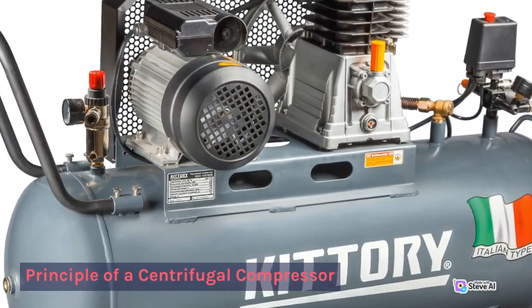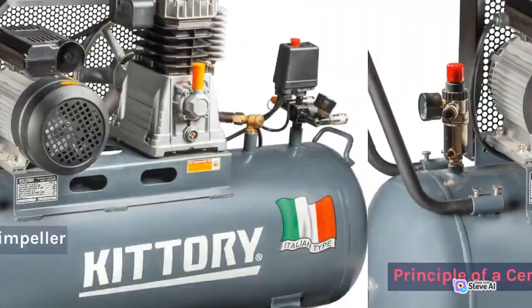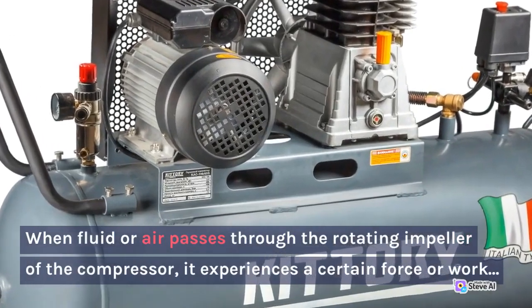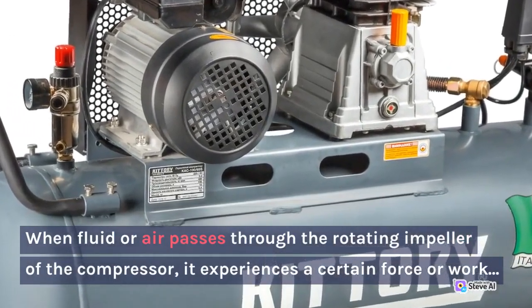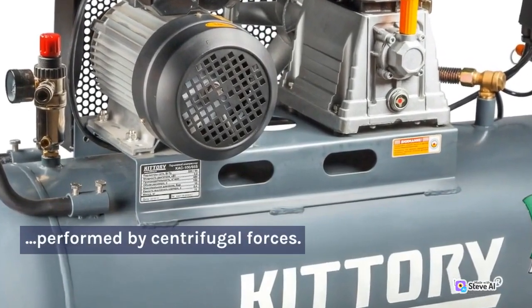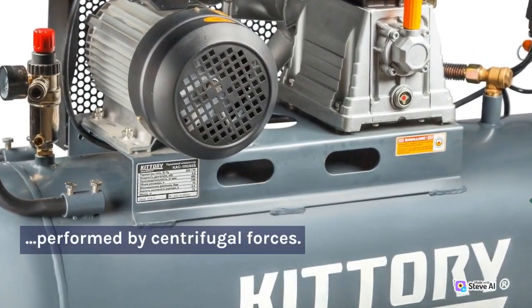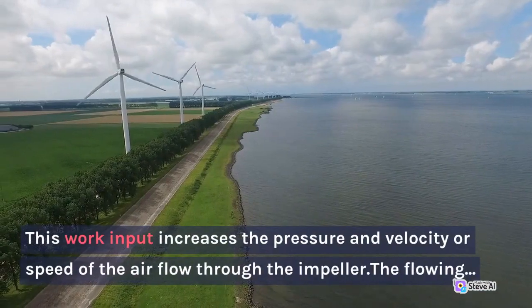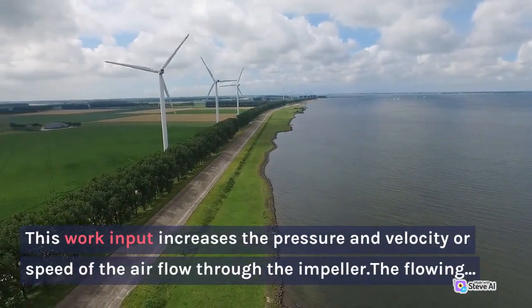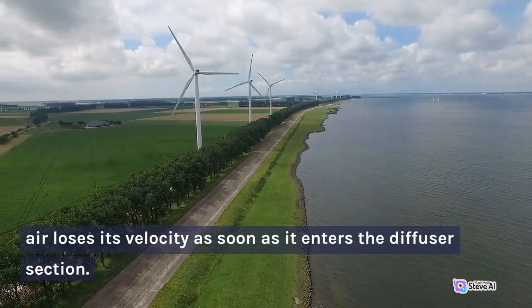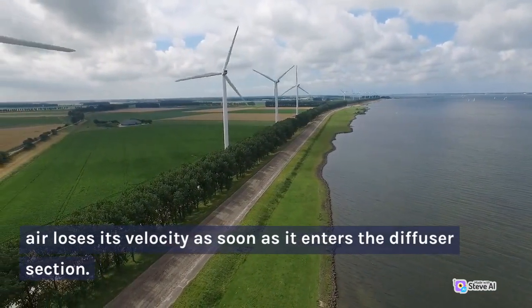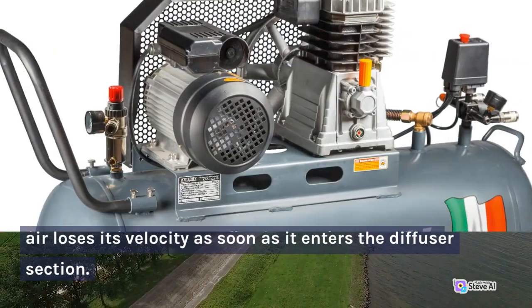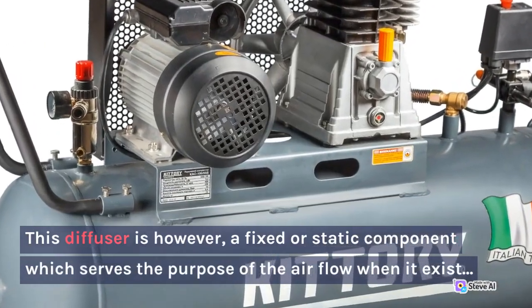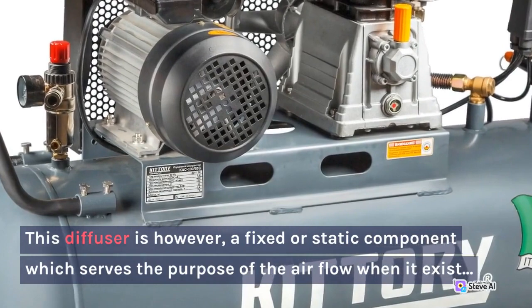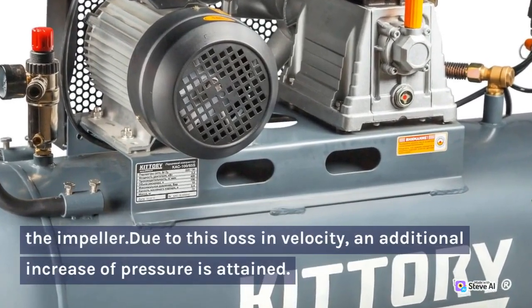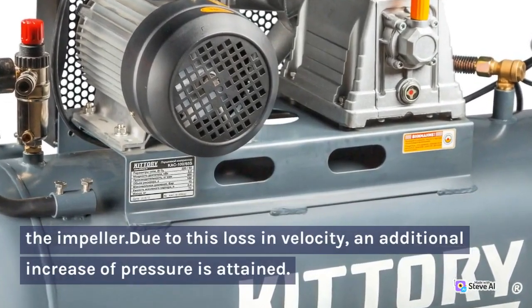Principle of a centrifugal compressor. When fluid or air passes through the rotating impeller of the compressor, it experiences a certain force or work performed by centrifugal forces. This work input increases the pressure and velocity or speed of the airflow through the impeller. The flowing air loses its velocity as soon as it enters the diffuser section. This diffuser is, however, a fixed or static component which serves the purpose of guiding the airflow when it exits the impeller. Due to this loss in velocity, an additional increase of pressure is attained.